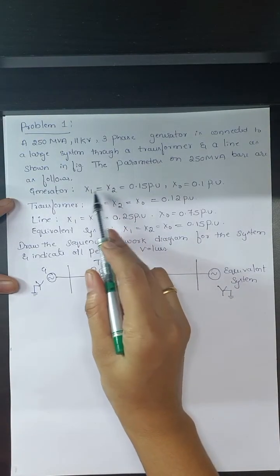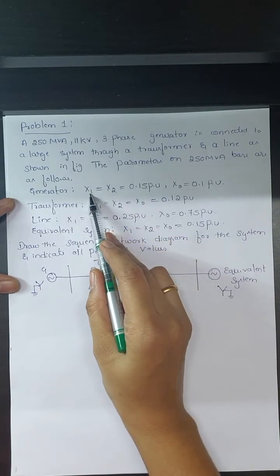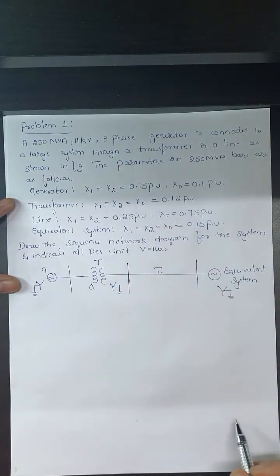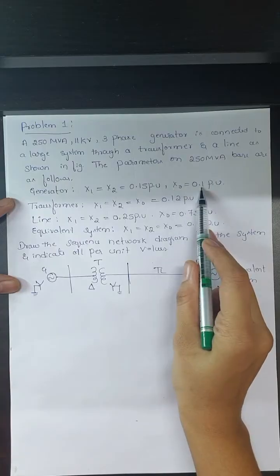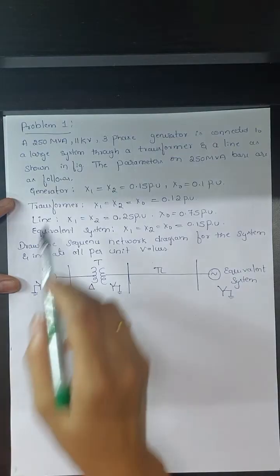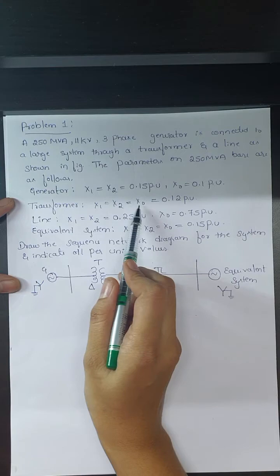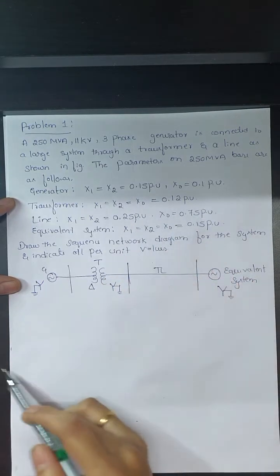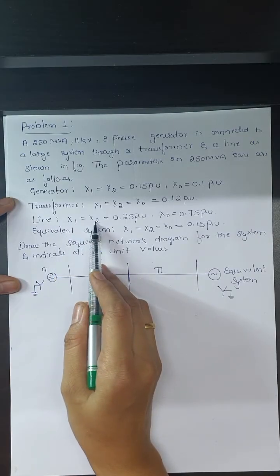For the generator: X1 (positive sequence reactance) and X2 (negative sequence reactance) are both equal to 0.15 per unit, and zero sequence reactance X0 is equal to 0.1 per unit. For the transformer: positive, negative, and zero sequence reactances are all equal to 0.12 per unit. For the transmission line: positive and negative sequence reactances are 0.25 per unit, and zero sequence reactance is 0.75 per unit.